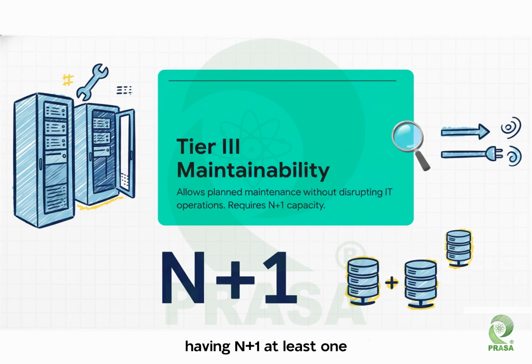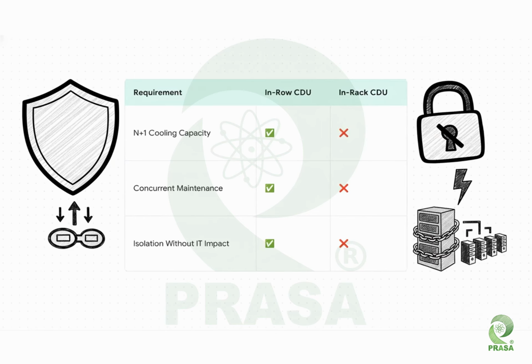The key to this is having N+1. At least one independent backup unit ready to go. And when we run our 2 contenders through the Tier 3 test, well, the result is pretty brutal. The in-row architecture, because you can have that backup N+1 unit, it checks every single box, no problem. The in-rack model, it fails completely, across the board.